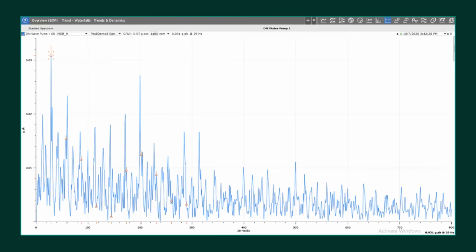Typically, it will attach a waveform or a spectrum to that piece of data that's in high alert status. Or if it's an alarm, the user may want to default and see as much data as it can, as often as it can. So the sensor will automatically default to its fastest scan time, and of course, it will automatically default back to its previously configured intervals. So the sensor itself has some embedded smarts and analytics here to help our operators.